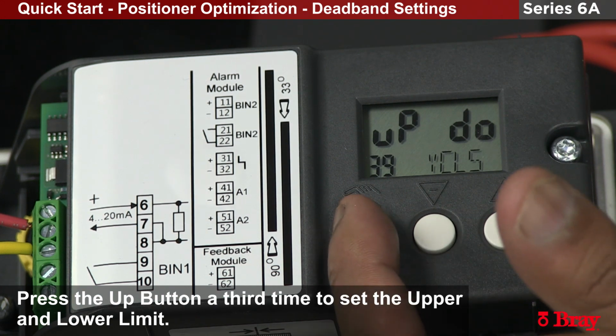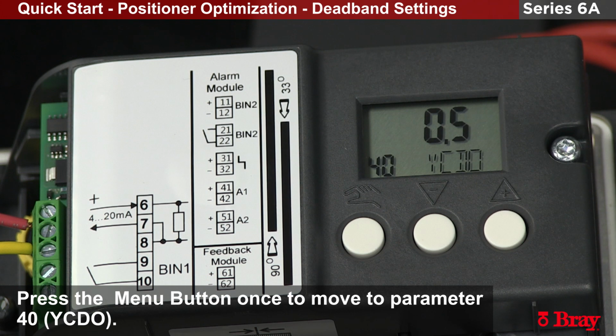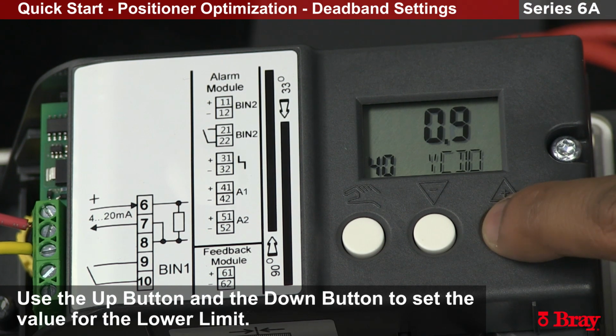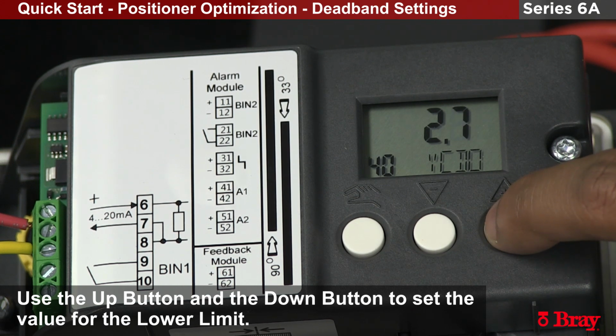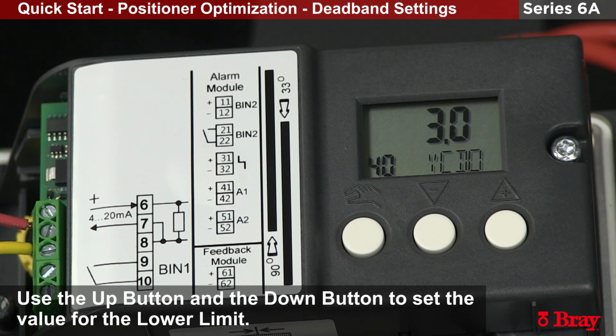We'll hit the hand button to go to the next window. This is where we'll set the value for the lower limit. From the factory here, as default, we'll do 0.5. We can increase this. We'll do 3%. So at 3% close, the unit will ignore loop power and go full close until a loop power signal comes back to the unit that is greater than 3% closed.